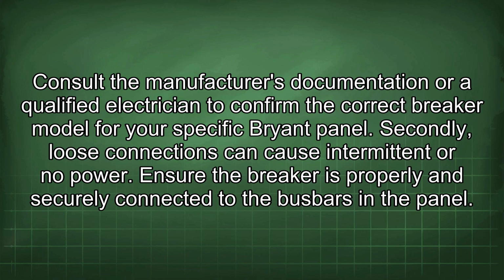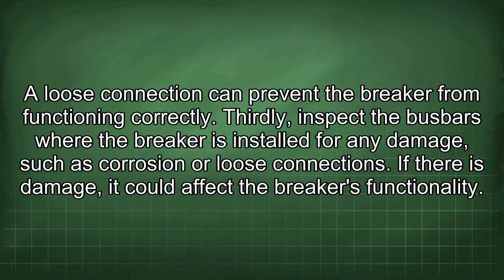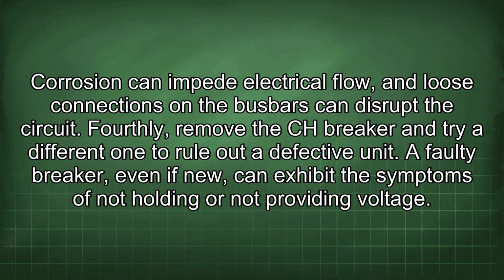Secondly, loose connections can cause intermittent or no power. Ensure the breaker is properly and securely connected to the bus bars in the panel. A loose connection can prevent the breaker from functioning correctly. Thirdly, inspect the bus bars where the breaker is installed for any damage, such as corrosion or loose connections. If there is damage, it could affect the breaker's functionality. Corrosion can impede electrical flow, and loose connections on the bus bars can disrupt the circuit.